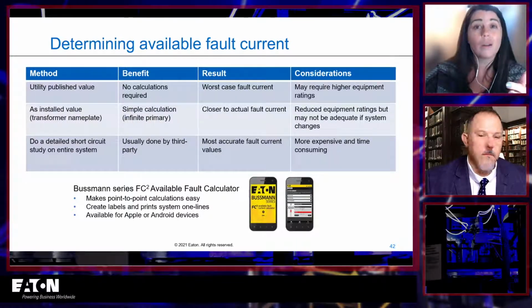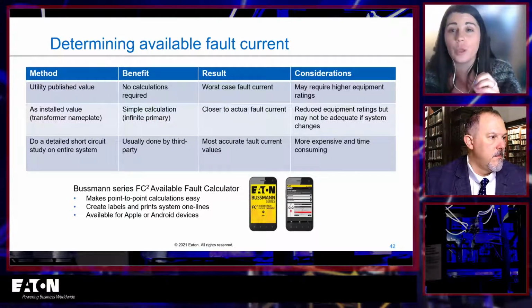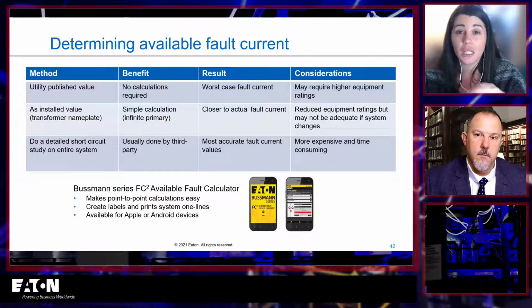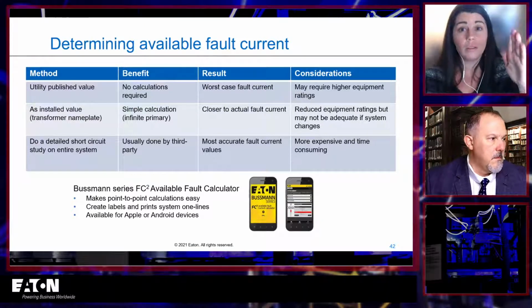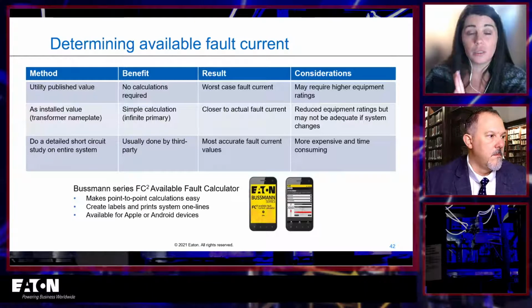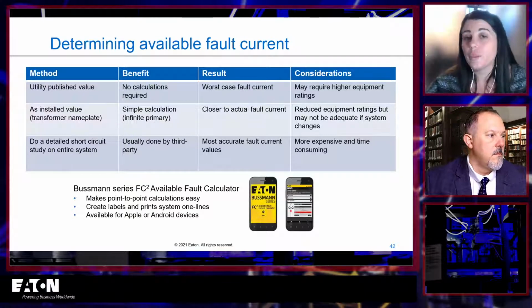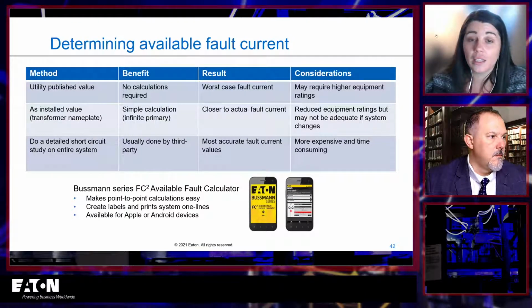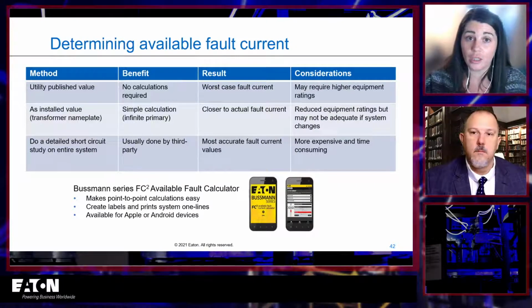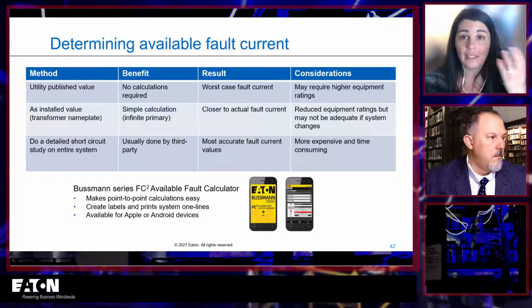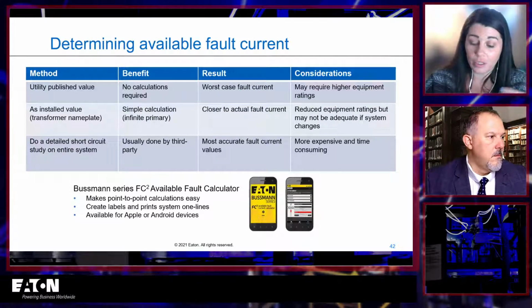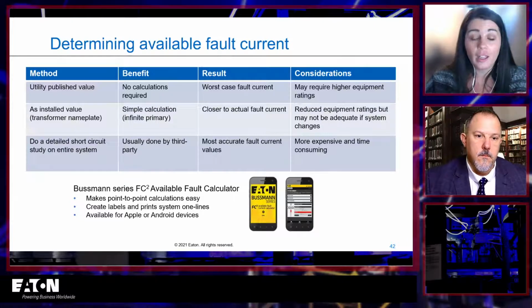A lot of times this is part of an arc flash study. So if you get an arc flash study done in your facility, step 1 is to do this, and then step 2 is to do the arc flash study. So it's included in that way. Obviously, you're going to get the most accurate values that you can get. It is the most expensive and takes the most amount of time. So sometimes you really just want that back of the envelope calculation, so use FC squared.